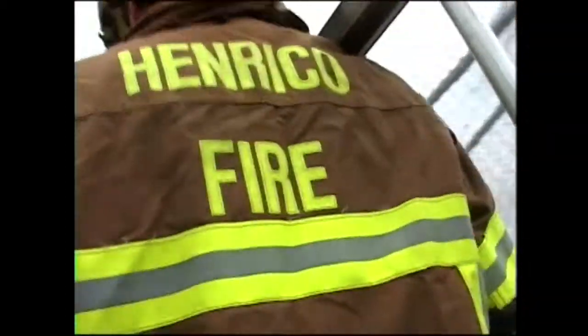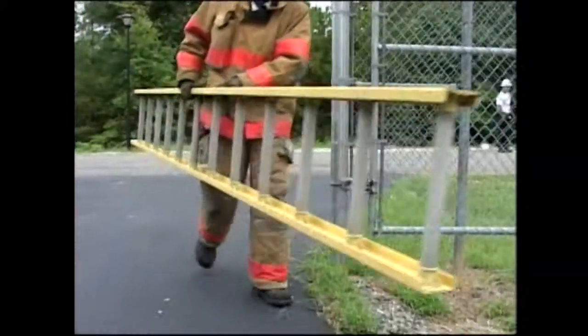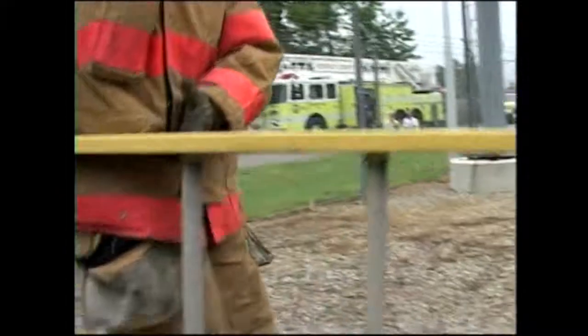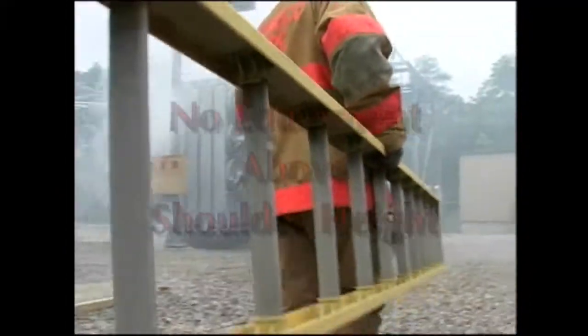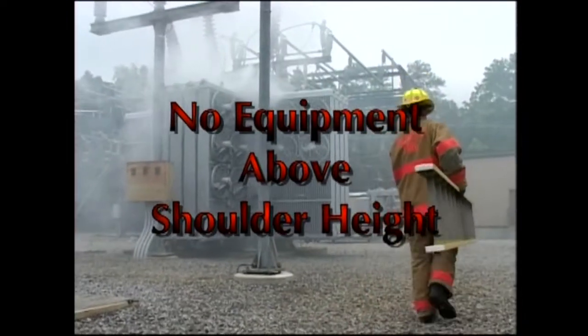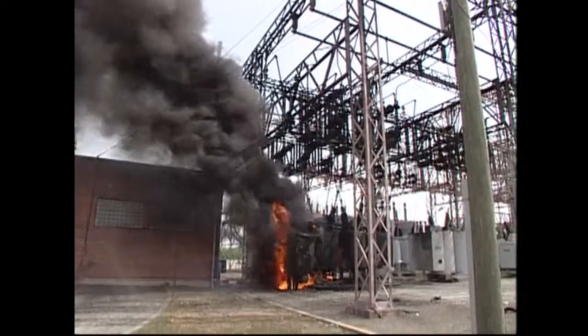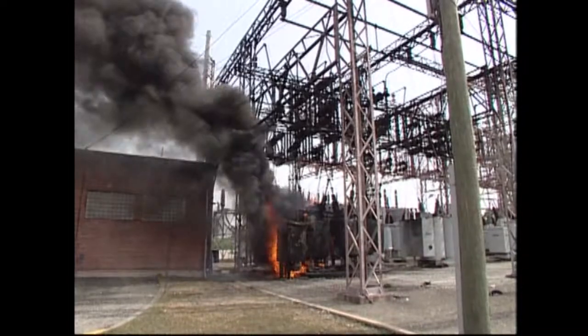They may decide to let the equipment burn itself out while directing firefighters to protect exposures. In situations like this, metal ladders should not be used. Only ladders made of non-conducting materials. A good guideline to follow when inside the substation is to have no equipment extend beyond shoulder height, because any overhead facilities may be energized.